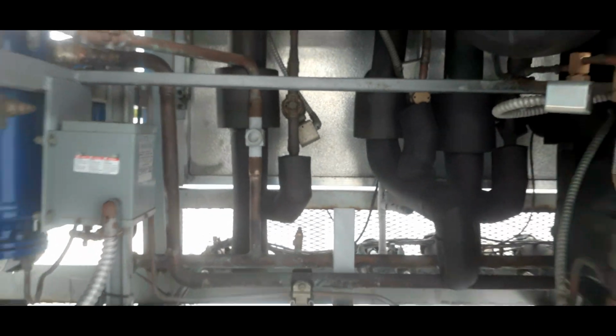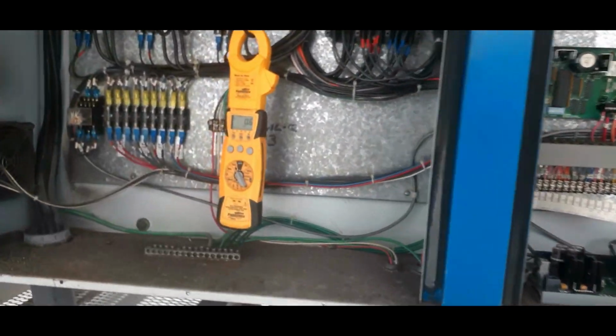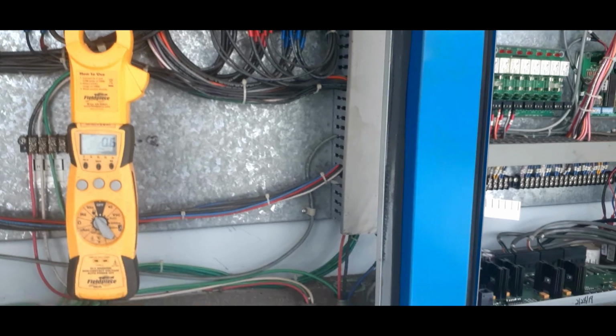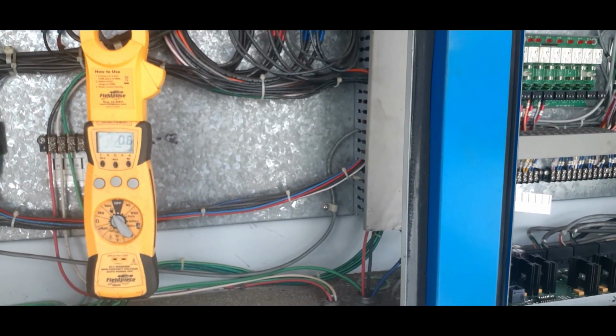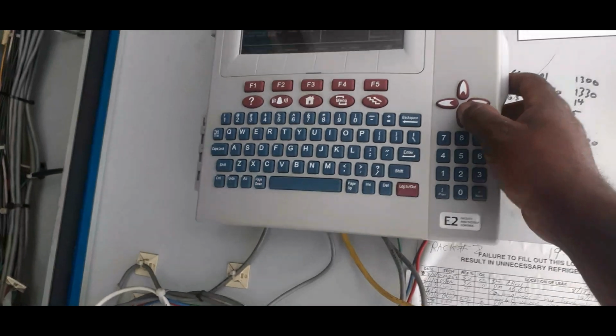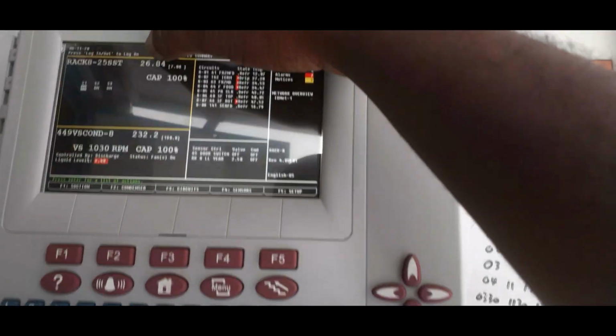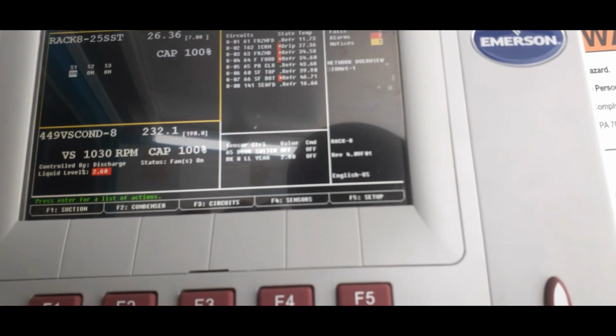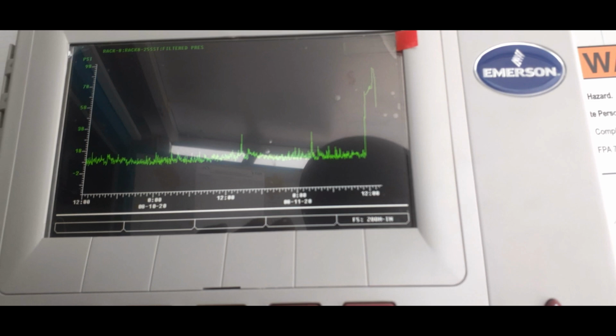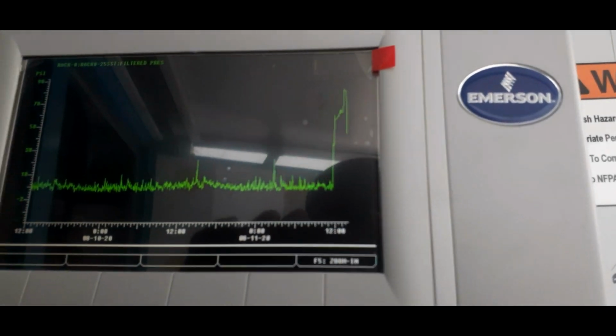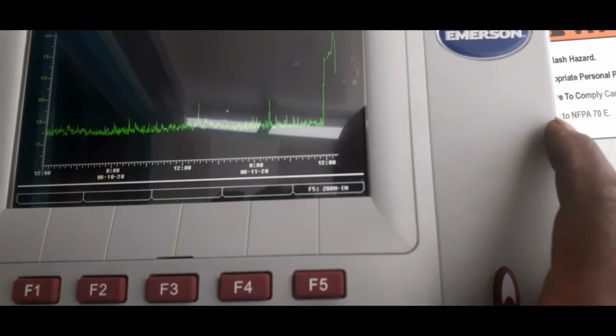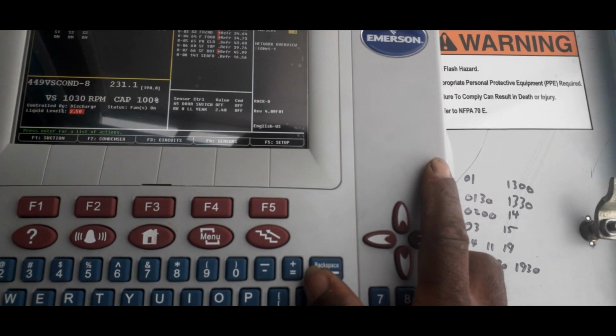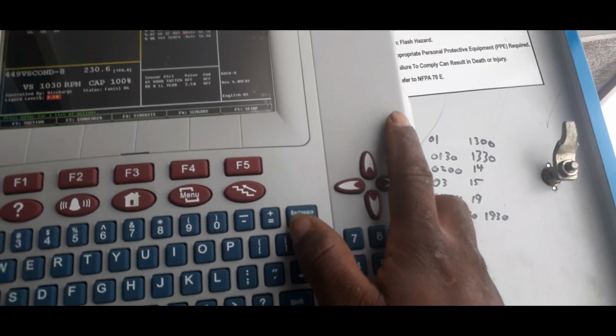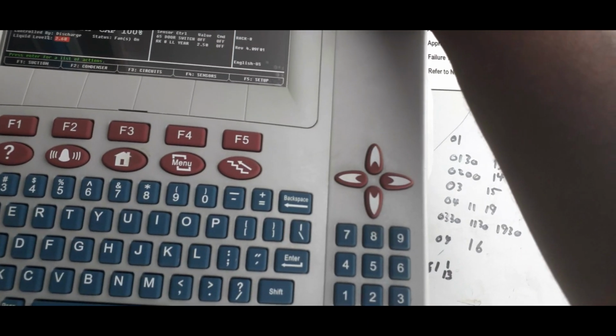Sight glass is clear. But this compressor is still off. Probably gonna flip that off. Let it cool down. I'll check it in a bit. So we're down to 26 now. 26 from, what was that? Yeah, look at that. Alright, so while it's pulling down, I'm gonna head down to my truck, go get the hot gas solenoid rebuild kit, and I'm gonna go ahead and rebuild that solenoid.